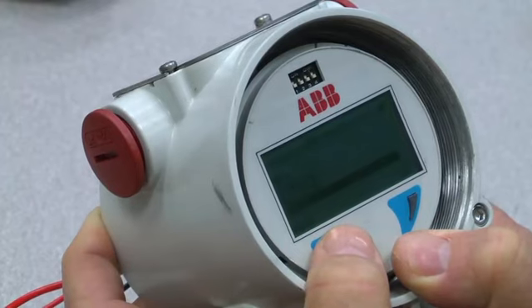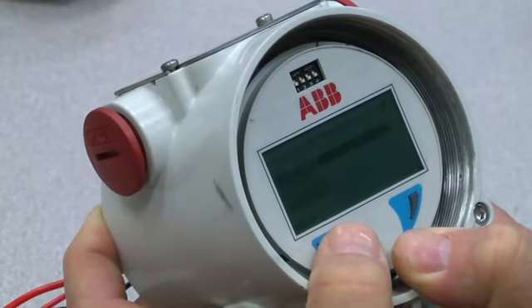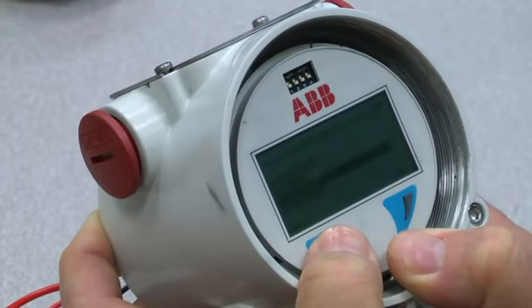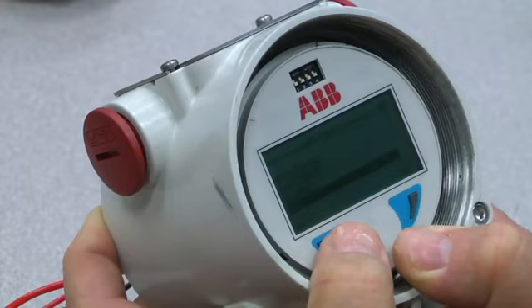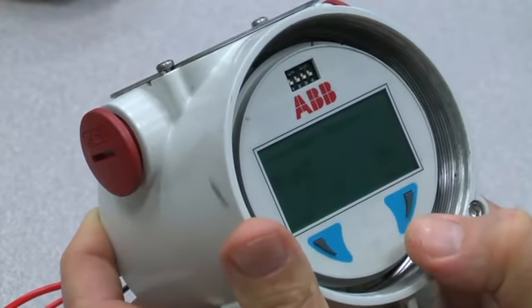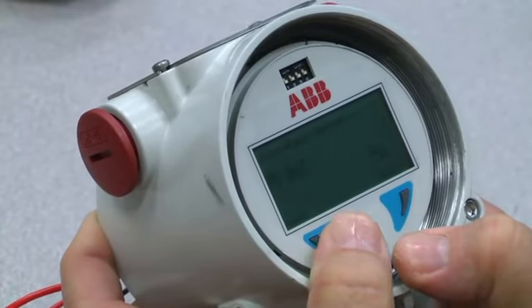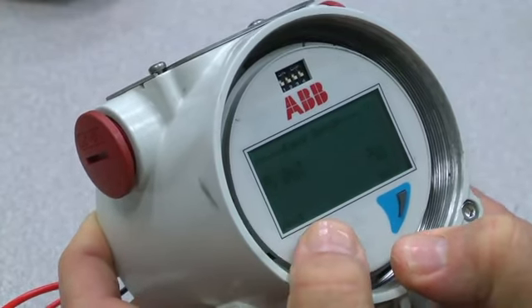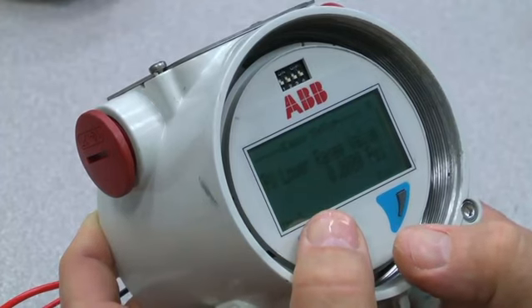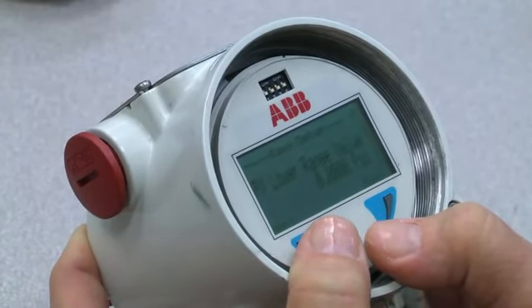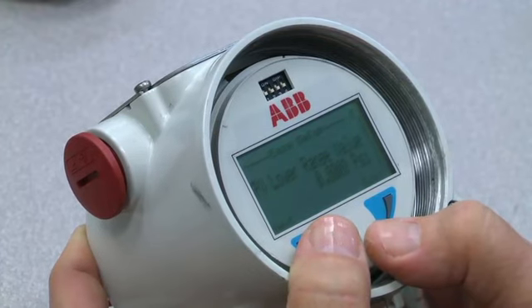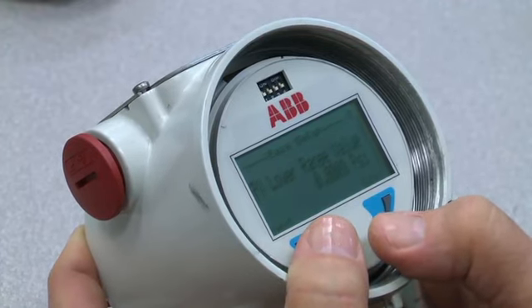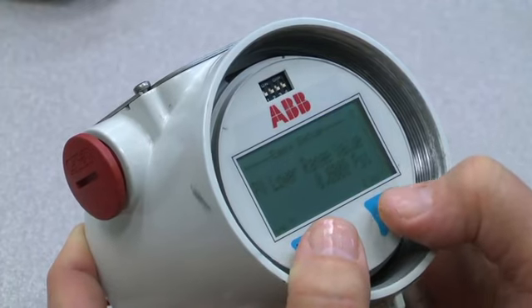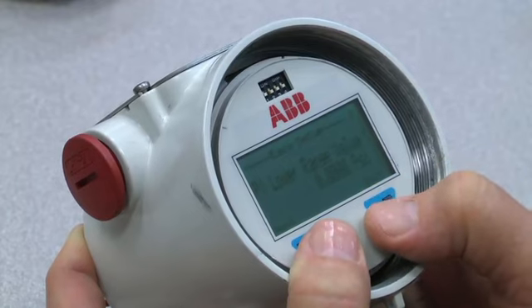And you can see there are quite a few different options. And then I'm going to make my selection. I'm going to go next again. And this is the process variable lower range value. If you're doing a calibration on the unit, for the PV lower range, you want to make sure that it's vented to atmosphere. And when you do the high range, you have to put pressure on it. So you're going to add pressure to the amount of the high range that you want to set that high range for. You can't just change it in the device and leave it like that.